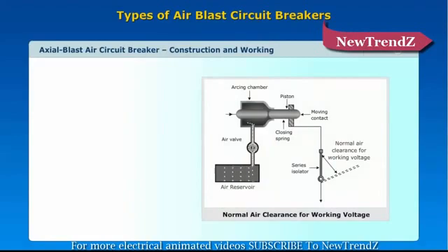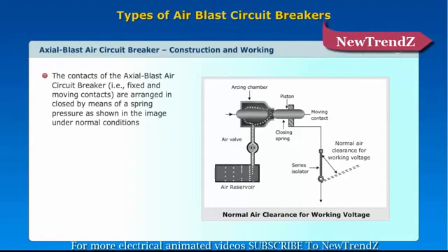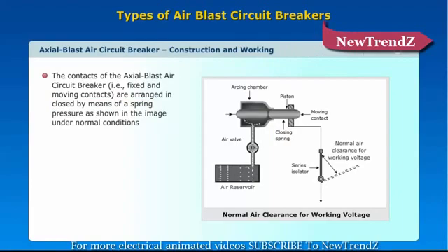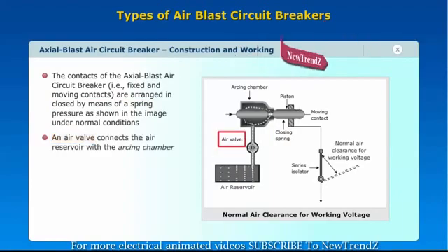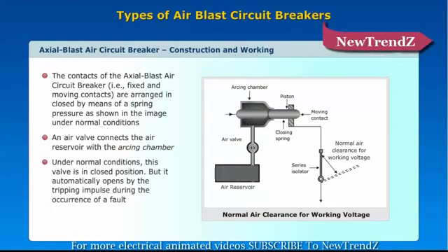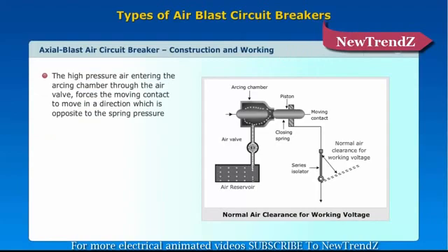Axial blast air circuit breaker construction and working. The contacts of the axial blast air circuit breaker — fixed and moving contacts — are arranged and closed by means of spring pressure, as shown in the image, under normal conditions. An air valve connects the air reservoir with the arcing chamber. Under normal conditions this valve is in the closed position, but it automatically opens by the tripping impulse during the occurrence of a fault. The high pressure air entering the arcing chamber through the air valve forces the moving contact to move in a direction opposite to the spring pressure.